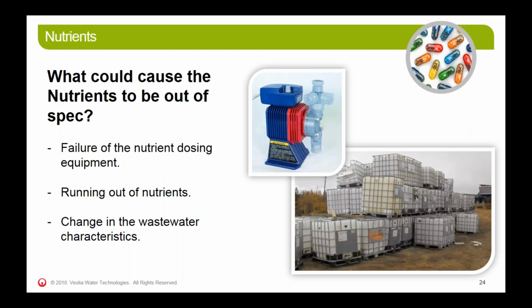So what could cause a problem with the nutrients? Most likely the failure of the nutrient dosing equipment. It's very rare that you have too many nutrients causing an issue. It's almost 99.99% of the time a lack of nutrients that's the problem. So you would have the failure of some dosing equipment, a dosing pump, or you would run out of nutrients. Or it could be a change in the wastewater characteristics. Let's say your influent water had enough nitrogen and phosphorus in it, and then because of a change of a product or a change in how something is operated, you don't have those anymore and you didn't know it, so you didn't have enough anymore. So that would be a change in wastewater characteristics. Next.